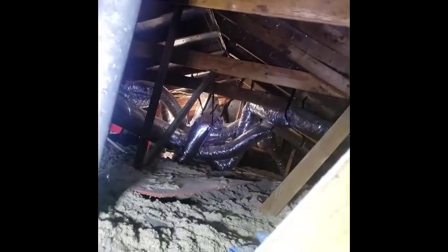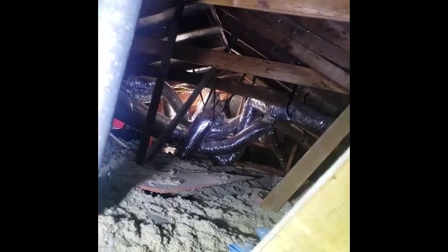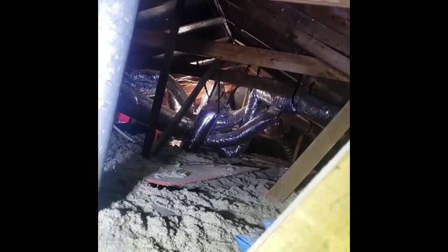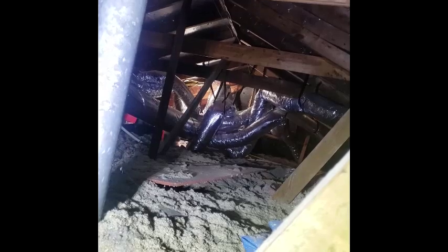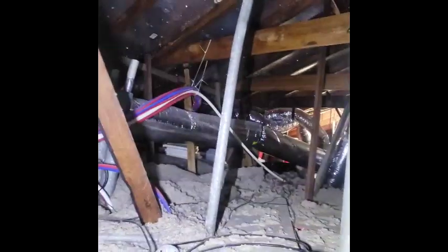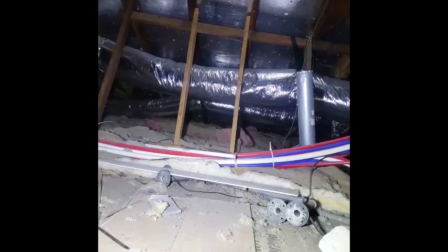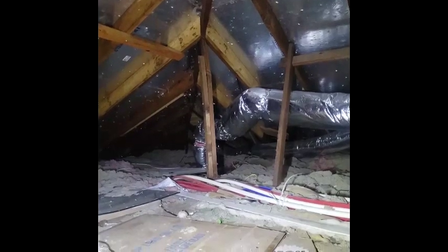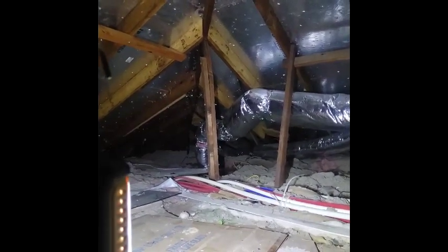Alright, so it's 2 entrances to the attic. But see that spider web of duct work, but that end of the house where the furnace is at, or the air handler, this side is cooling, getting too cold, and there's no dampers to adjust the airflow to get more air to this end of the house. And you see that's probably about a 30-foot run where they use, I think that's 10 or 12-inch duct. Let's see if I can get a 10 or 12-inch duct with this part of the house where the living room is at. I think he said they added this part on. I'm not sure, but I think this side of the house was an add-on.